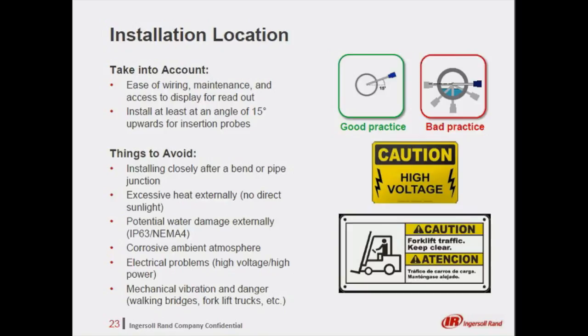Careful attention should also be made to avoid installing closely after a bend or pipe junction, excessive heat on the unit or in direct sunlight, potential water damage or corrosive elements external to the pipe, electrical problems as a result of high voltage, and excessive vibration from walking bridges, vehicles, and process equipment.